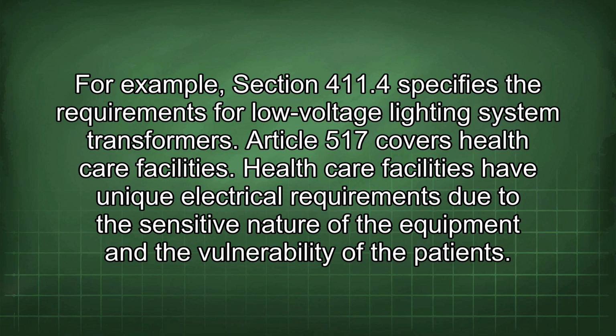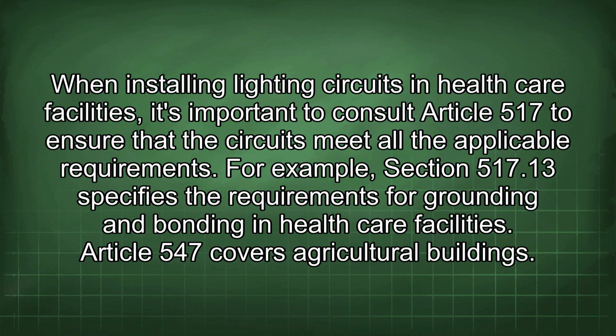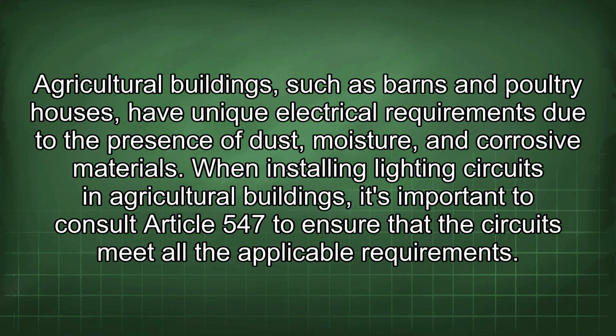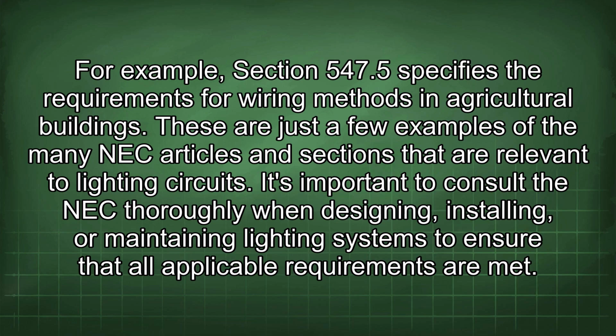Article 517 covers healthcare facilities. Healthcare facilities have unique electrical requirements due to the sensitive nature of the equipment and the vulnerability of the patients. When installing lighting circuits in healthcare facilities, it's important to consult Article 517 to ensure that the circuits meet all the applicable requirements. For example, Section 517.13 specifies the requirements for grounding and bonding in healthcare facilities. Article 547 covers agricultural buildings. Agricultural buildings, such as barns and poultry houses, have unique electrical requirements due to the presence of dust, moisture, and corrosive materials. When installing lighting circuits in agricultural buildings, it's important to consult Article 547 to ensure that the circuits meet all the applicable requirements. For example, Section 547.5 specifies the requirements for wiring methods in agricultural buildings.